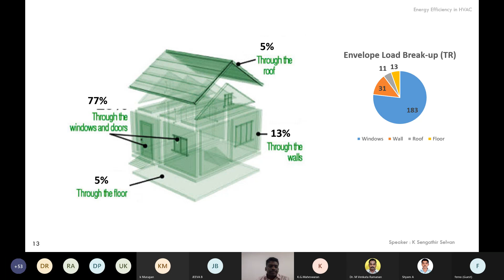Okay, so generally, there are two methods of heat ingression through the fenestration. One is through radiation, and another is through conduction. So now we have taken single glazing as the base case. So here, 47% of our heat ingress through windows is by means of conduction. Now, if we improve the U value of this glazing by going with double glaze, yes, there will be a slight savings. But however, the majority of the heat gain is through solar, SHGC, I mean solar heat gain through radiation.